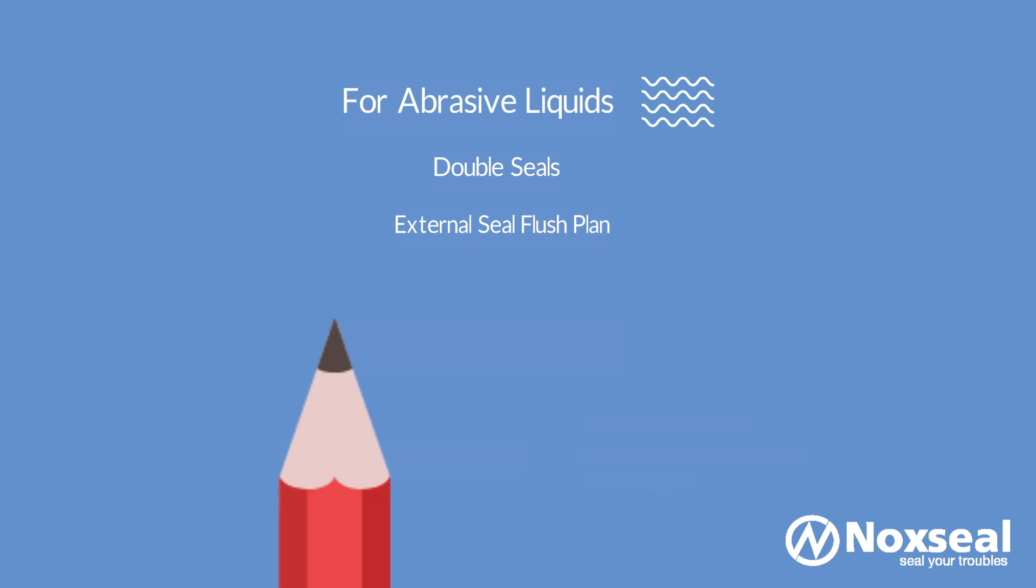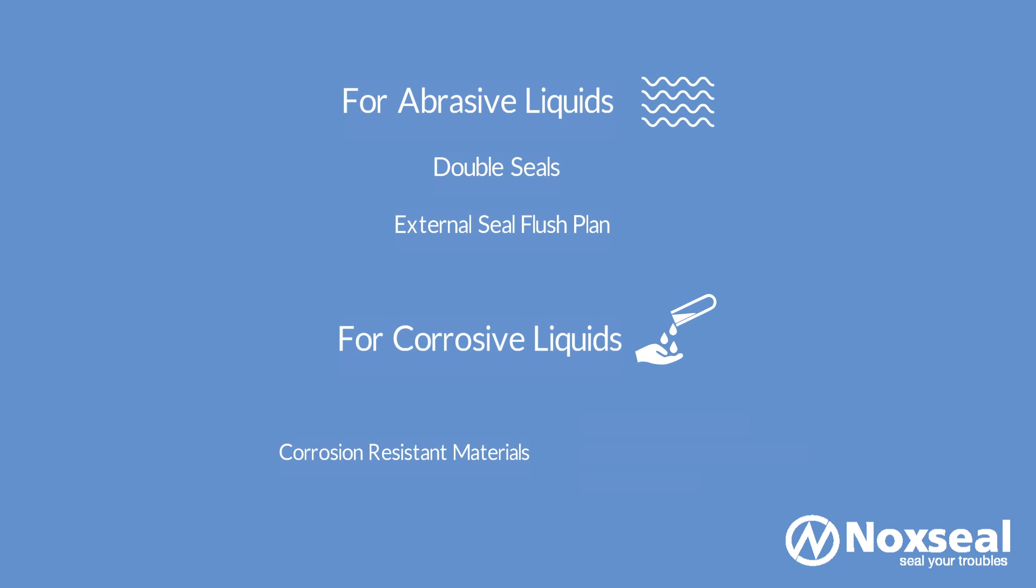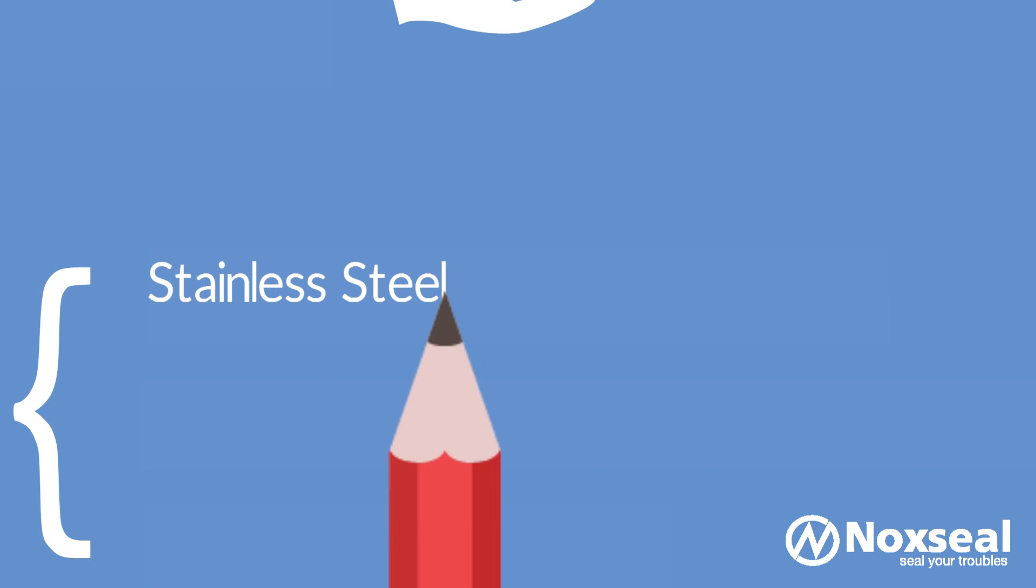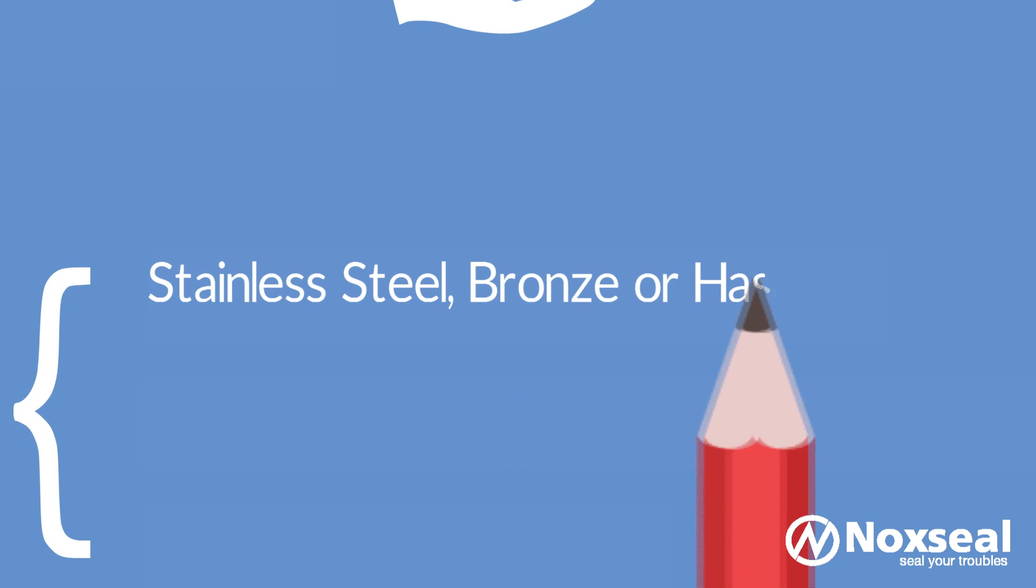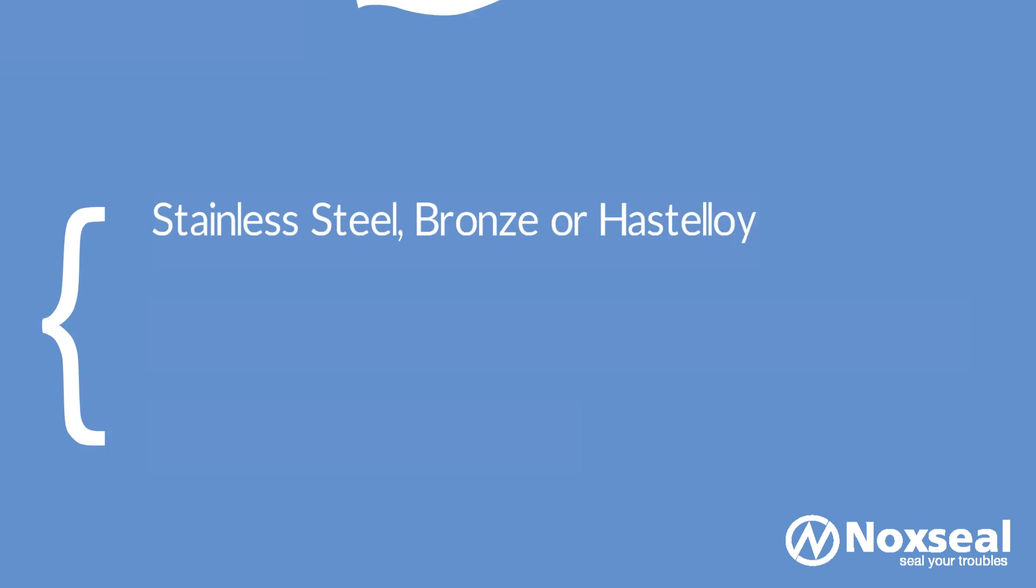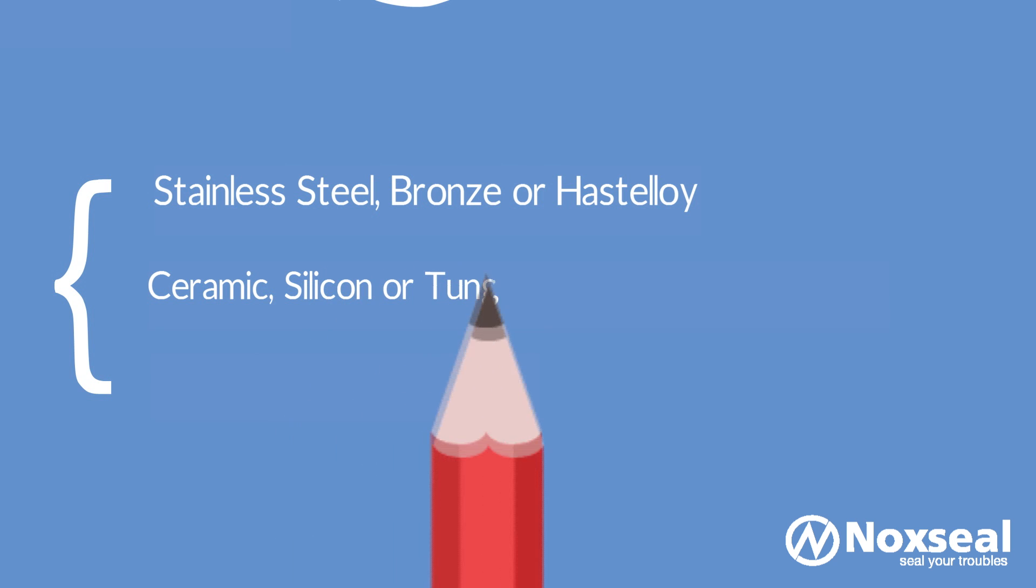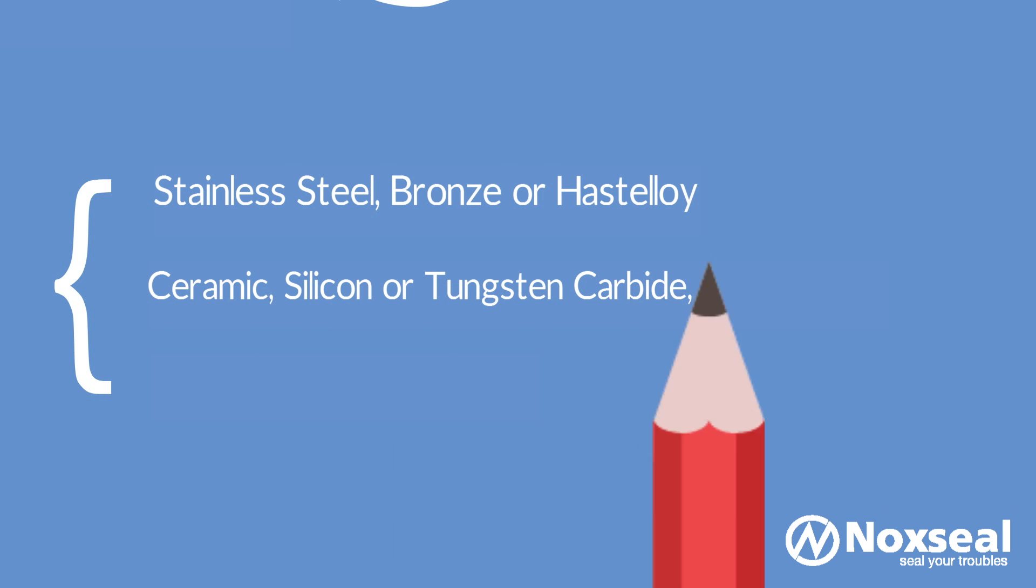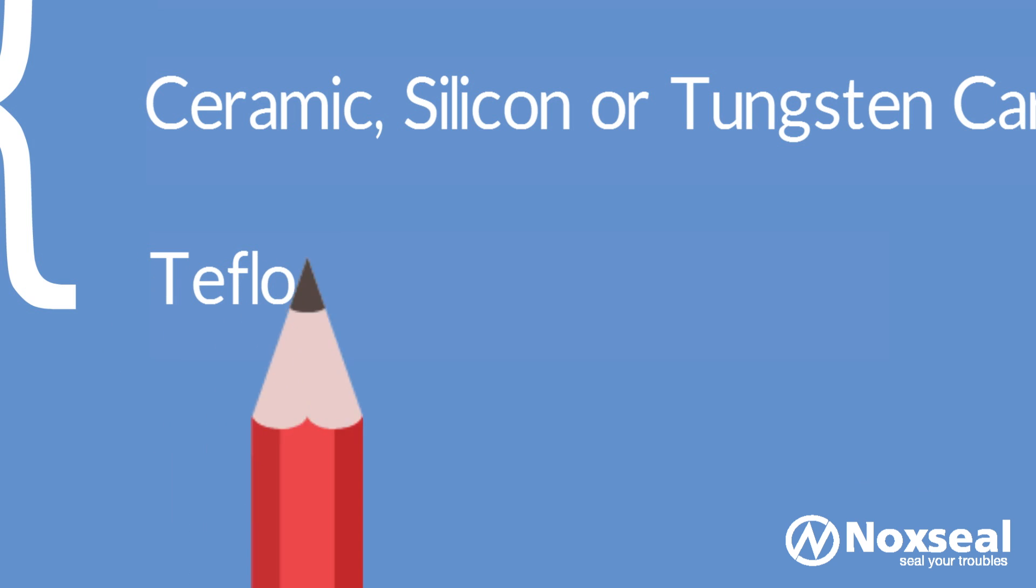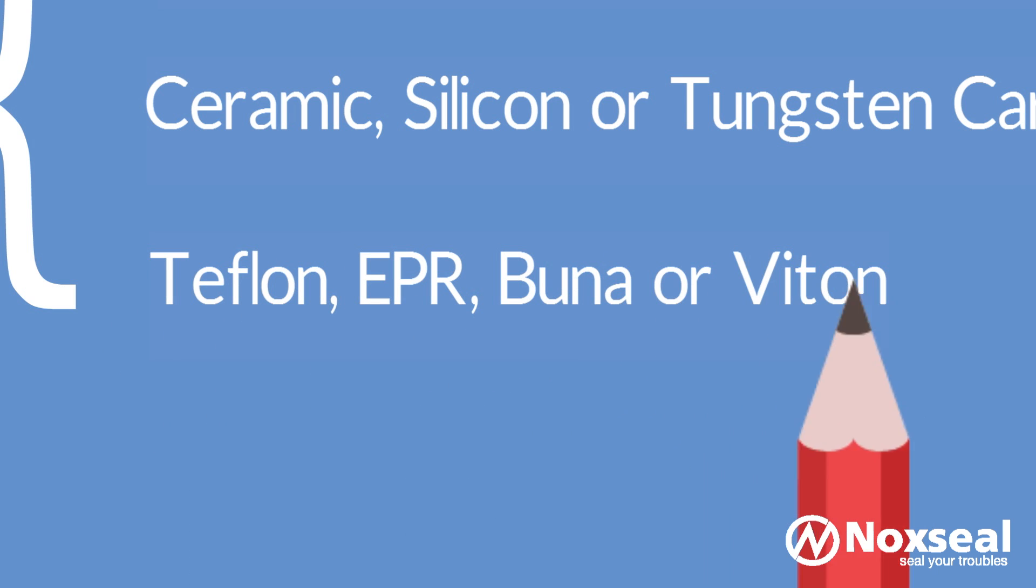For corrosive liquids like acids, it is important to select corrosion-resistant materials, such as stainless steel, bronze or Hastelloy, for the mechanical seal. The mechanical seals also comprise of the mating surfaces and these should also be made up of corrosion and wear-resistant materials like ceramic, silicon or tungsten carbide, carbon, etc. The stationary parts of the mechanical seal can be Teflon, EPR, BUNA or VITON.